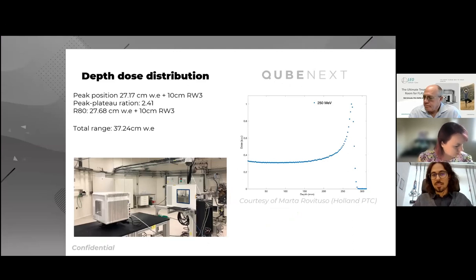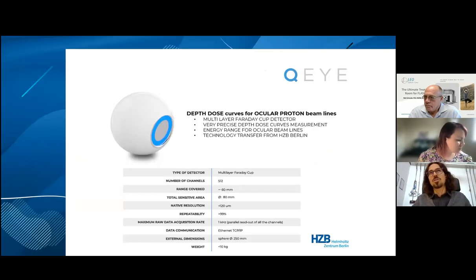Basically, that was tested up to 50 nanoamps at the target at 250 MeV, and so we obtained the Bragg curve as well. Of course, this is not conceived for that kind of measurement. It's for conventional rates, to have a monthly QA of the peaks of those measurements.